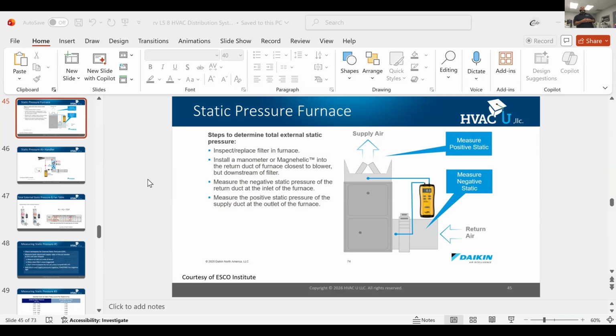So for example, where you're headed, a 1 inch pleated filter is really restrictive. I've seen some articles that it had the same pressure drop as a piece of cardboard. And it might be best to upsize that filter to increase the surface area so that you can reduce your static.